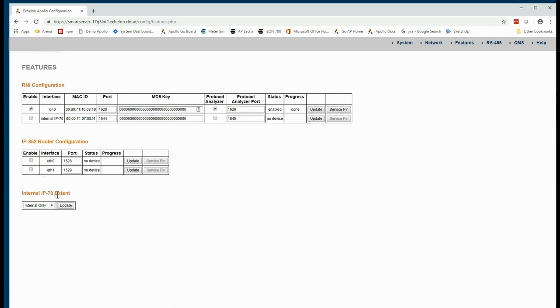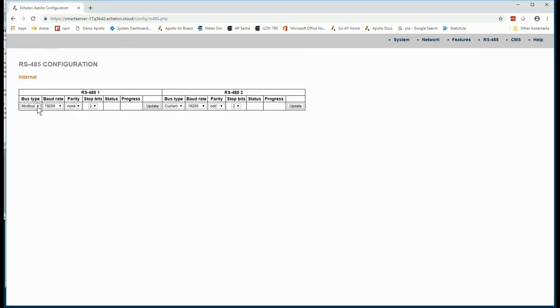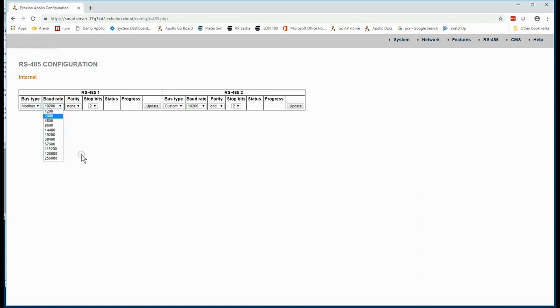If we're building a large network with an IP852 backbone, we can enable that here, as well as turn on the IP-70 extent for external app management. Finally, in the RS-485 tab, we are able to select which protocols run on the two RS-485 channels and also the characteristics of the serial data.